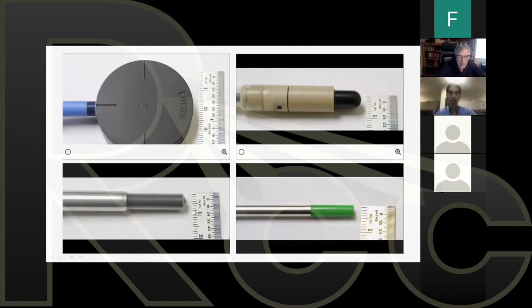Okay. So for TG51, which is the US protocol, I use a Farmer chamber. It's called a Farmer chamber, and it's made by PTW. And this is it right here. It's a waterproof chamber made by PTW. Can you see it on the screen? Can you see the one that I'm pointing to? Right here? Okay. This is the one that I use for my absolute calibration. It's a 0.6 cc Farmer chamber made by PTW. Okay?